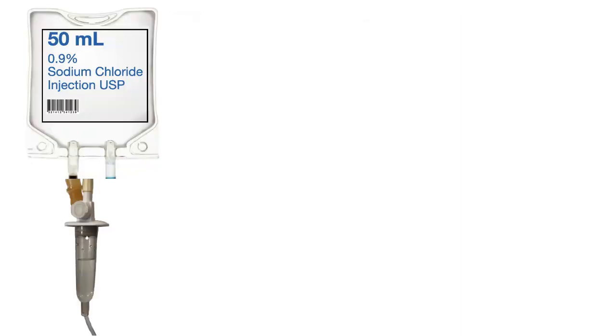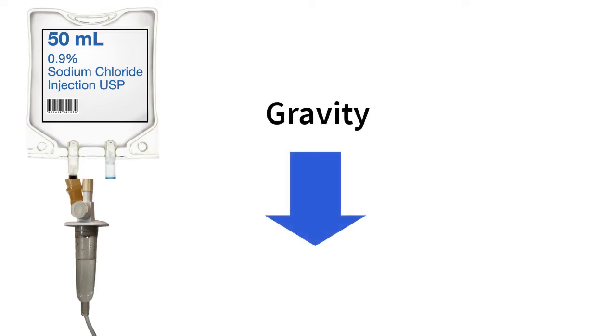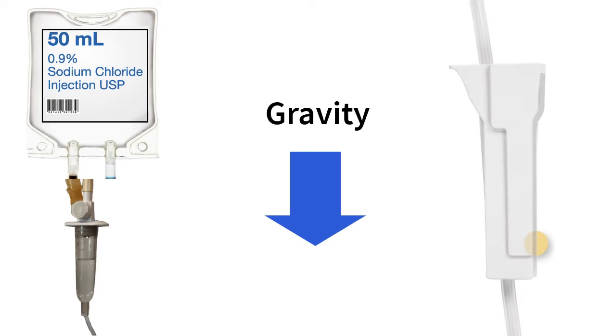Another type of infusion is one in which electricity is not required to infuse the fluid into the patient. Instead of being regulated by a pump, these infusions use the force of gravity. A clamp on the tubing is used to manually adjust the speed in the chamber.